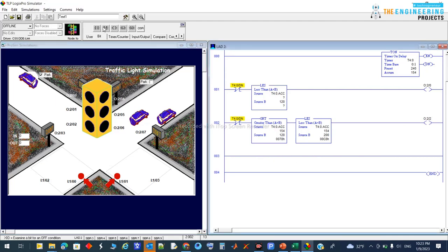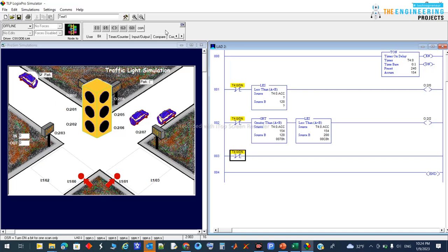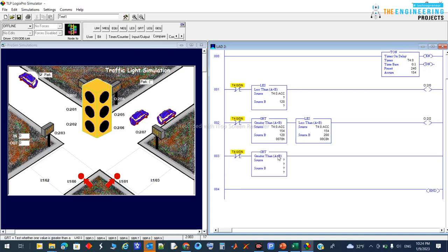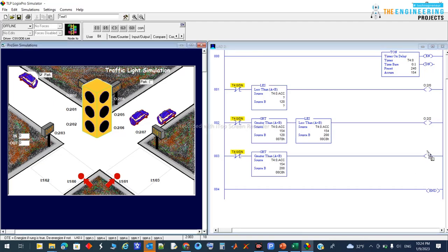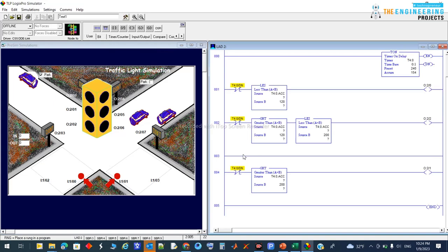Finally, adding the last rung for the yellow light. After 20 seconds — so if T4:0's accumulator is greater than 200 — that means greater than 20 seconds — I will run the yellow light output. But I also need the process to repeat after the timer completes its full cycle.